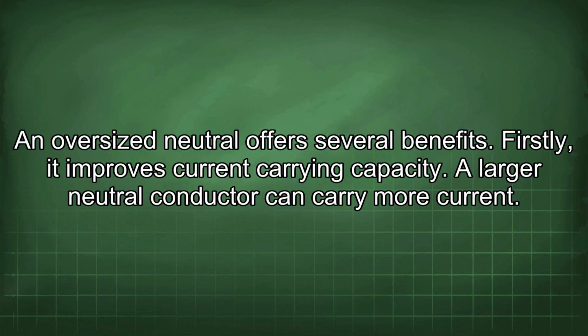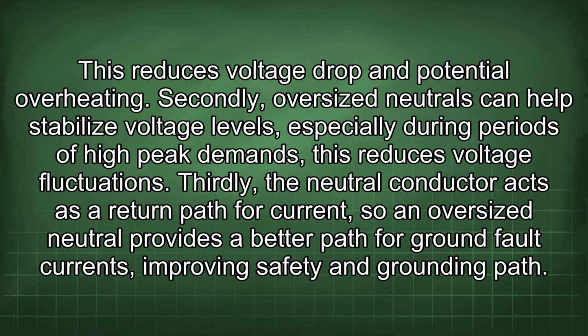An oversized neutral offers several benefits. Firstly, it improves current carrying capacity. A larger neutral conductor can carry more current. This reduces voltage drop and potential overheating.